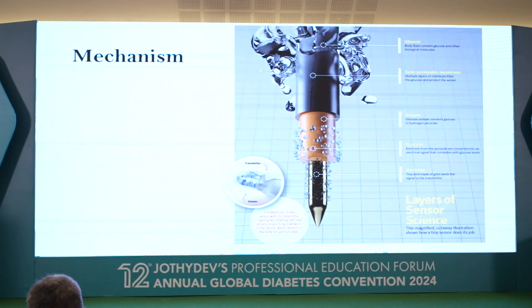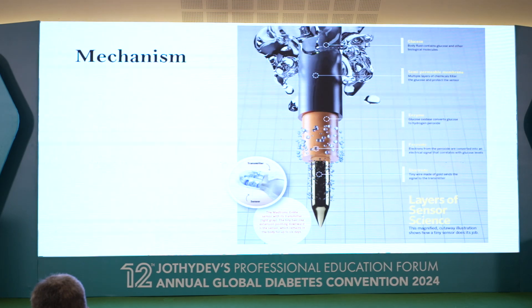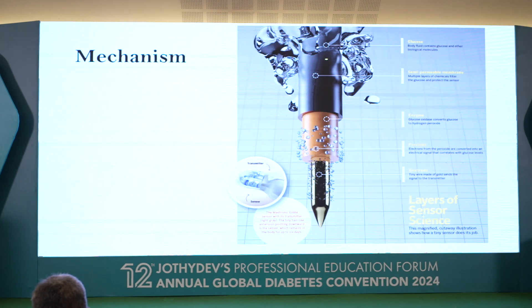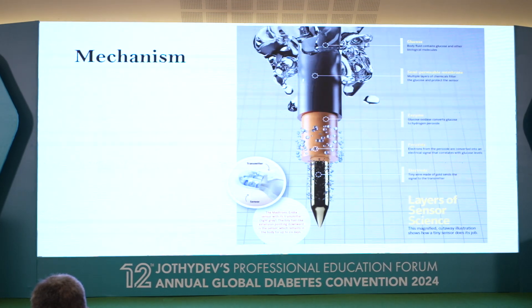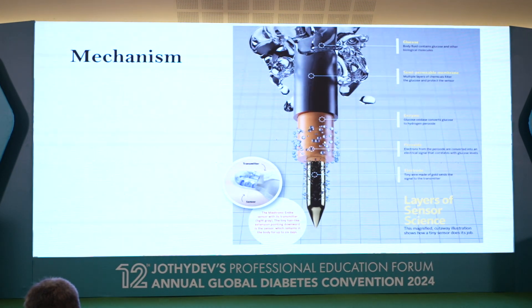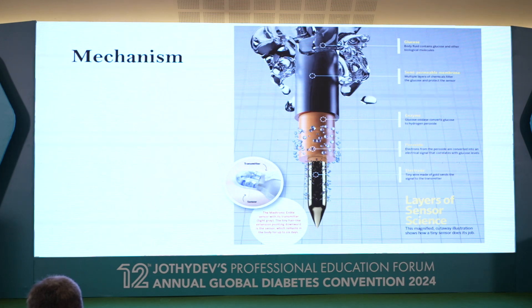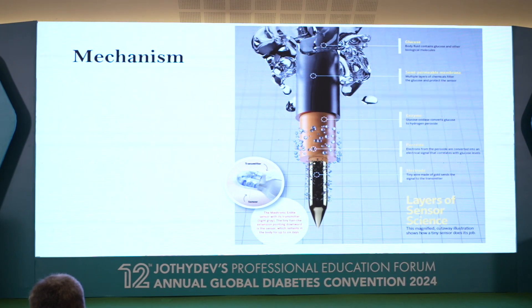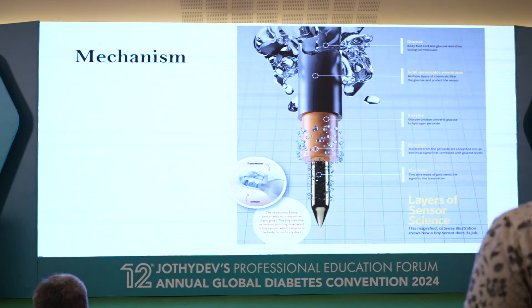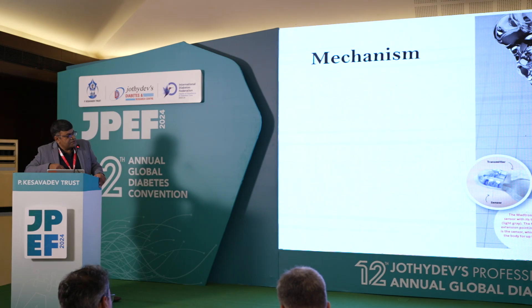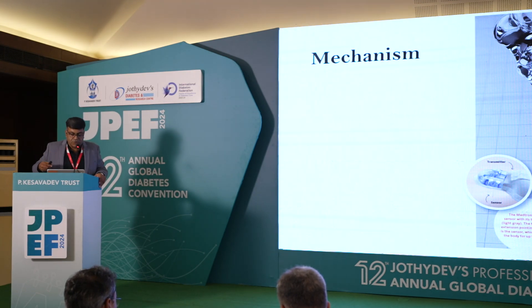This is a microscopic image showing how it works. At the outside there is glucose in the interstitial fluid, and there is a semi-permeable membrane which allows glucose to enter inside but other chemicals do not. After that there is an enzyme which converts the glucose into hydrogen peroxide, and during that process electrons are released. These electrons are sensed by the electrodes in the innermost layer, and the electric current generated is proportional to the glucose levels — that is how glucose levels are estimated.